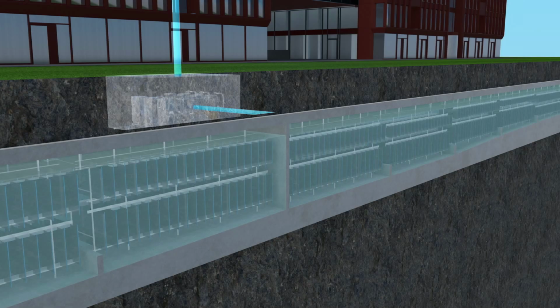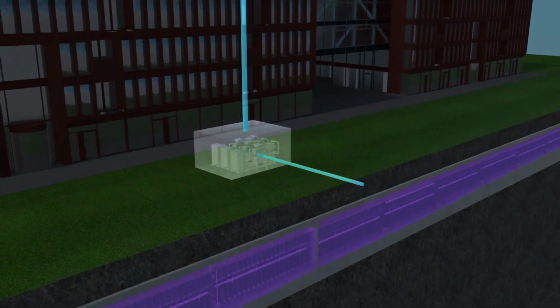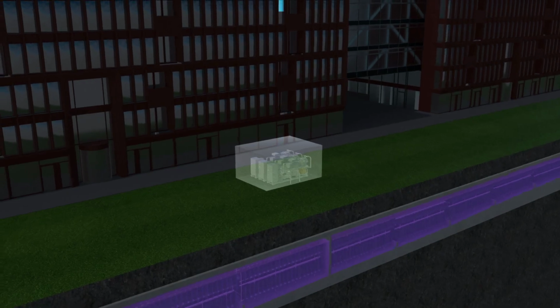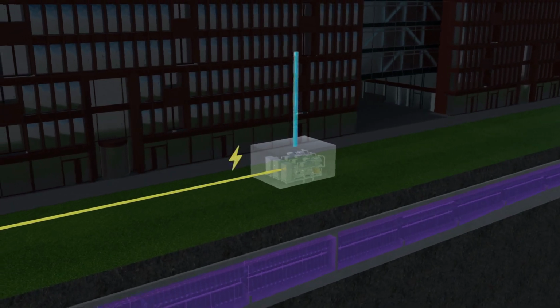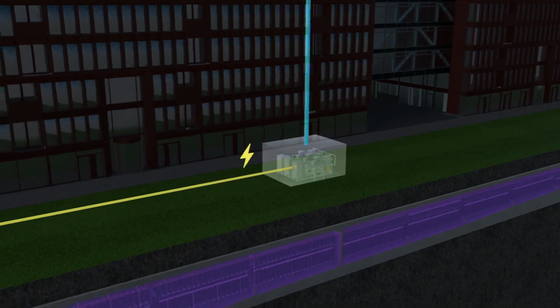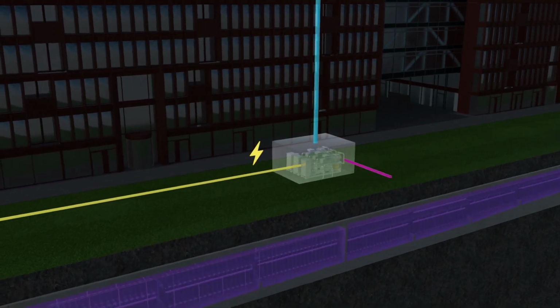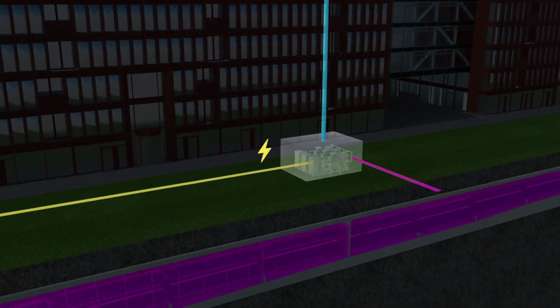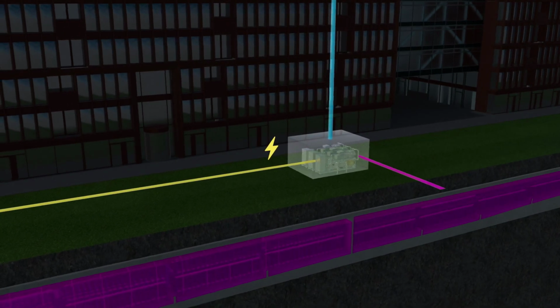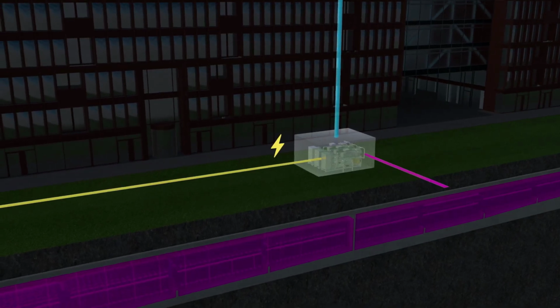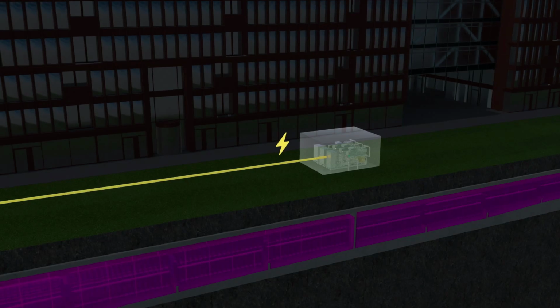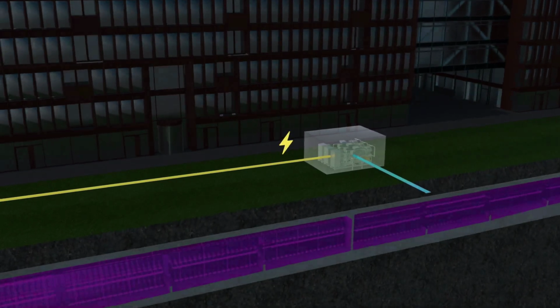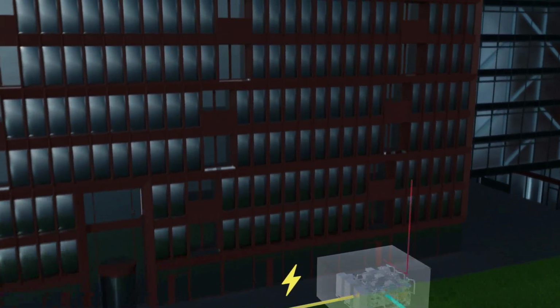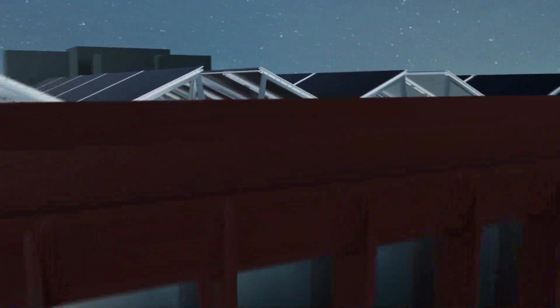By August at the latest, the ice will have completely melted, and the water in the reservoir will be warmer than 15 degrees Celsius. Now it can no longer be cooled directly either. The heat pumps now produce cold for the building again. The resulting heat then flows into the large water storage tank. However, the water storage tank must not be heated up too much. At night, the heat pumps then cool the storage tank down again. The waste heat that has been collected is released back into the night sky via the heat exchangers of the PVT modules.